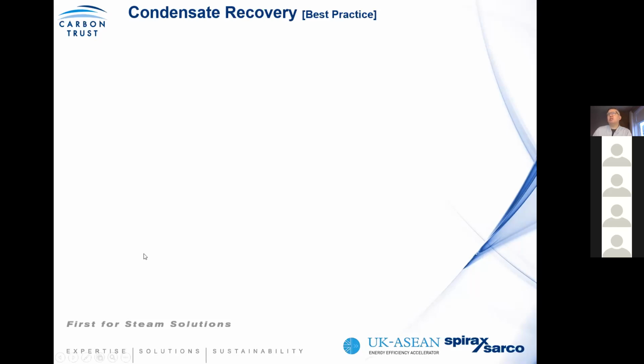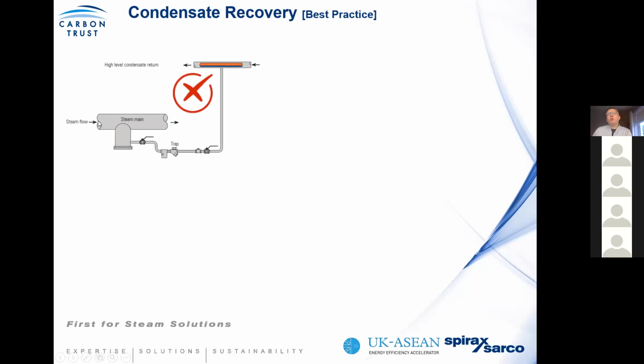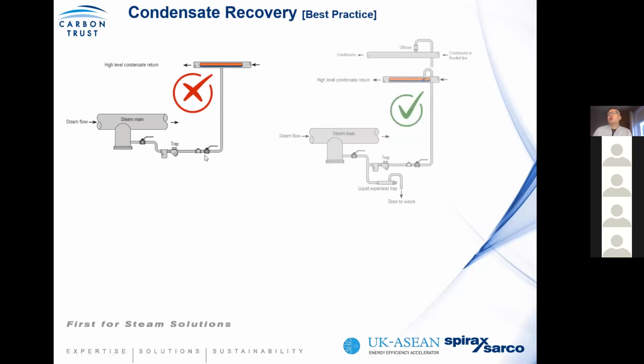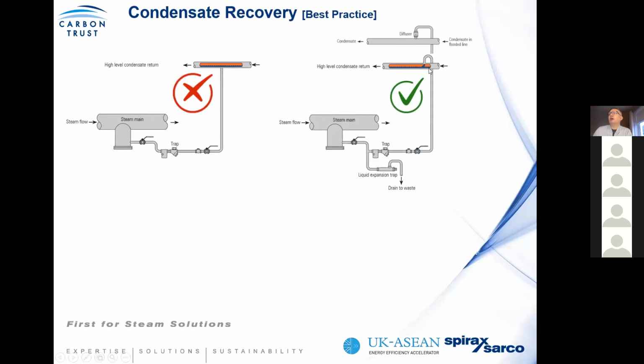So let's consider some additional best practices. One, we spoke about the trapping, but it's also important to understand how you interconnect to your condensate system. Again, we're seeing case examples where the traps are installed and interconnected to the base of the condensate system. Like the steam system, any condensate that is in this distribution header will basically backfall under gravity into the system, making it difficult for this trap to operate effectively. What you should do is, from your trap outlet through your riser, interconnect to the top of the pipe. So in other words, the condensate in this pipe should fall under gravity to its receiver. And in doing so, you're not discharging into what is effectively a flooded header.